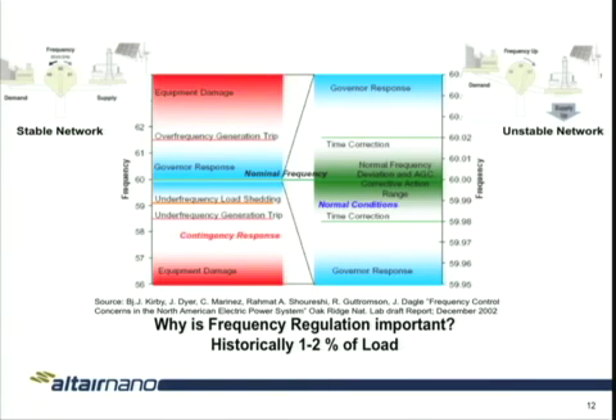So as we go through here, now this scale on this side is zoomed right in, right around 60. You can see now it's 59.95 to 60. And so here's your normal deviation with the automatic generator control corrective action range. This is where the signal is being sent based on the area control error that's being looked at, all the different boundary areas. And they are telling the generators, hey, you guys, speed up or slow down to maintain this, and it's going on every 4 seconds, getting that signal.